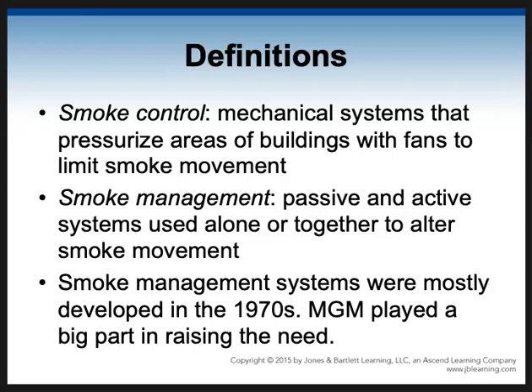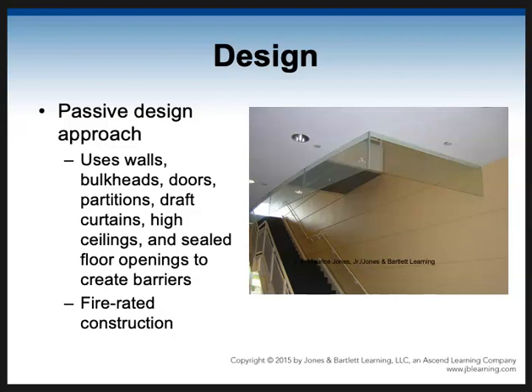When 79 people die just because the smoke went right into the stairwells, into their hallways, and people were found who were trying to escape, lying dead, unburned, unscarred, just dead from smoke inhalation in the hallways. So the three ways is, first one is passive. We're going to use passive designs like walls, bulkheads, doors, partitions, draft curtains, high ceilings. There's a reason why when you're in Walmart, Costco, Bevmo, Home Depot, Lowe's, that high ceiling in there, it's there for multiple reasons, but one of them is to keep smoke away from the people. And you're going to see other passive things in those kind of buildings. I'll show you a picture here in a second.